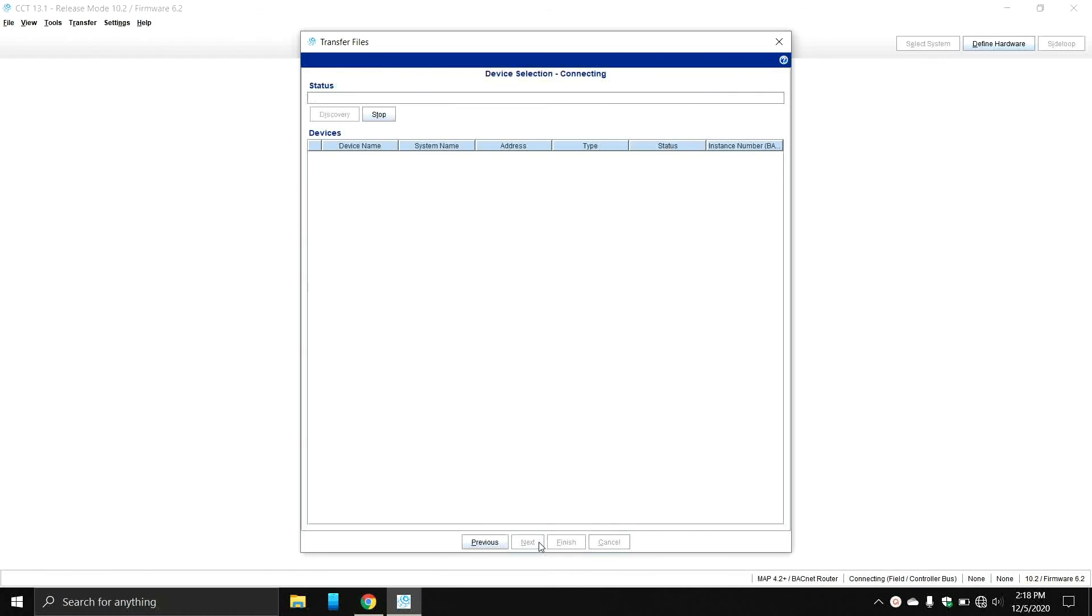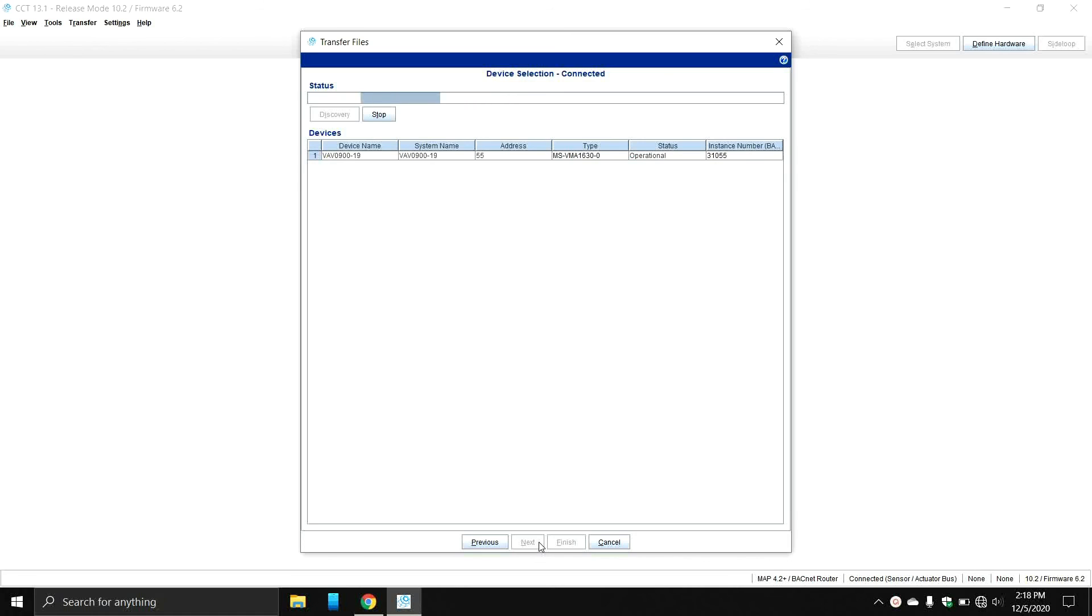The next thing we're going to do is go to your network interface and choose your WiFi card. Click next. Then everything should look pretty familiar at this point to you. Wait for it to scan. And there we go. We're using our MAP tool and we can see our one VAV that I'm hooked up to right now.